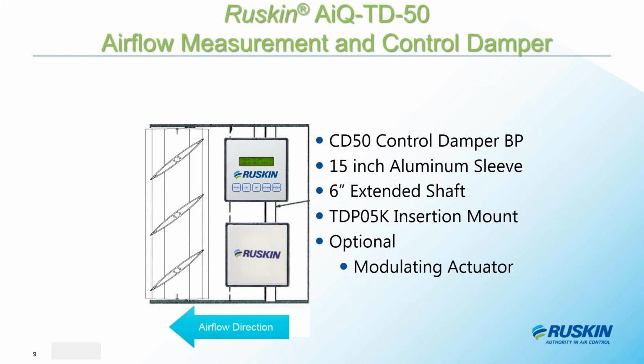So you would typically have a sleeve that's undersized by 1/4 inch for slip fit into existing ductwork. The direction of airflow is always through the air measurement section first and then out through the control damper. It will not work the other way unless it's a two-position damper, just open or closed. But air measurement is typically done to provide control of that airflow, and so it's usually a modulating damper. As an option, we can add any brand modulating actuator and have that installed at the factory, or the contractor can provide and install the actuator of their choice.